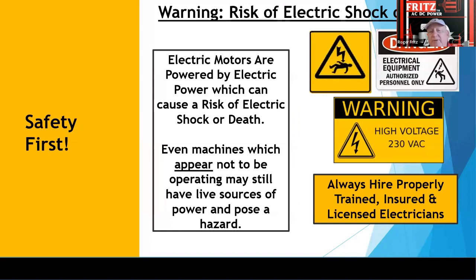We always try to bring up that because this technology is high voltage, people use extreme care when they open cabinets, arc flash. A lot of times they'll have capacitors built inside. So when you take the covers off, they have a residual voltage for a little while. Normally it's a 5-minute thing. So you normally want to wait at least 5 minutes once you take the covers off. Or if you do take the covers off, make sure that power is totally down so that the discharge capacitors have time to drop out before somebody starts putting their hands in there.